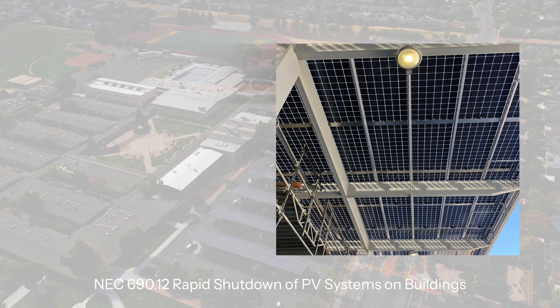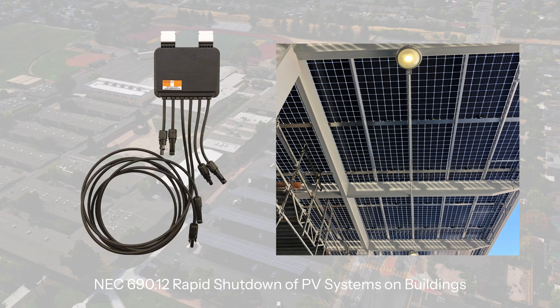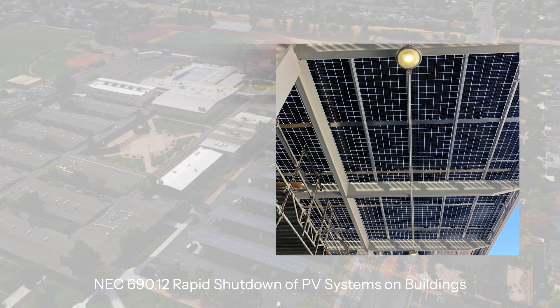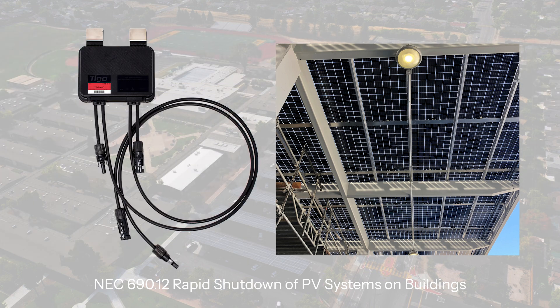This ensures the safety of first responders and technicians. All the Tigo rapid shutdown MLPEs meet the NEC 690.12 rapid shutdown specifications from 2014, 2017, and 2020 when installed on each PV module.